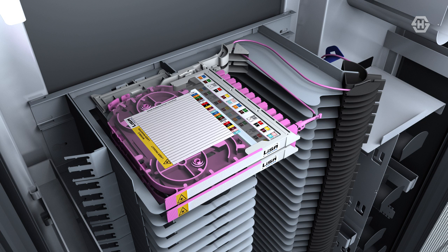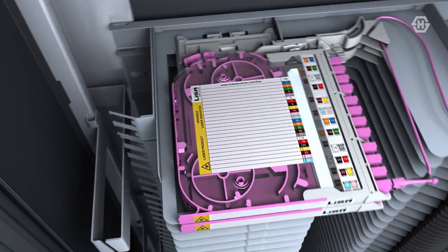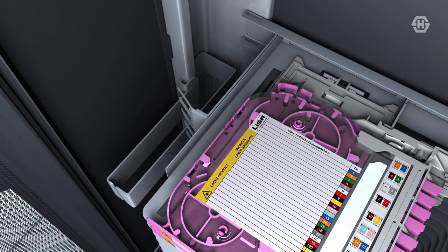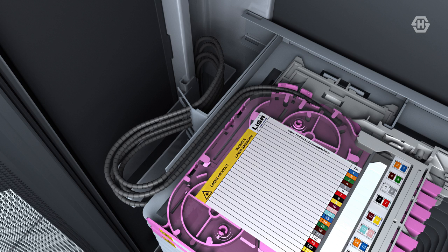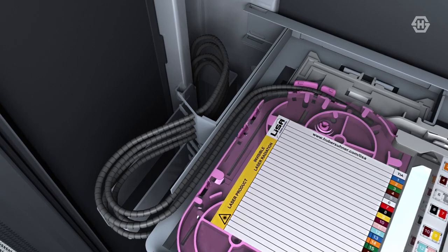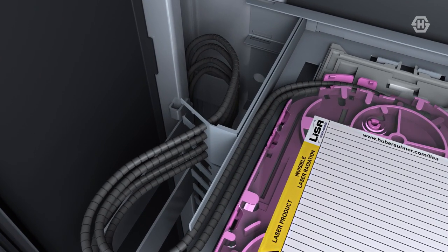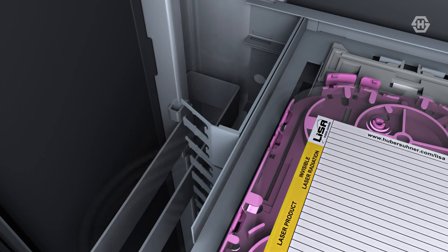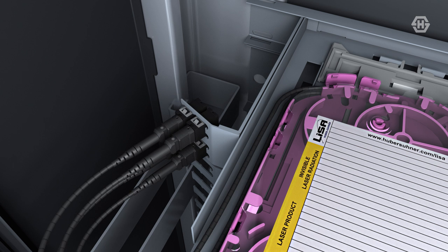This gives an overall density of 80 trays in a standard NGR configuration. Cables enter the tray unit from the rear left-hand side, where they are routed to a universal fixing bracket. Protective conduit from loose tube cables can be snapped into a special slot detail, or alternatively, MPO adapters can be inserted into the square apertures provided.